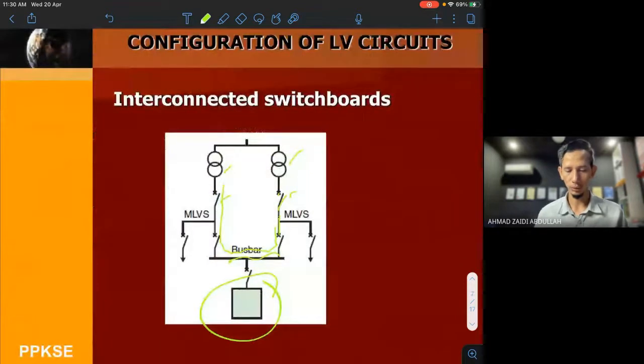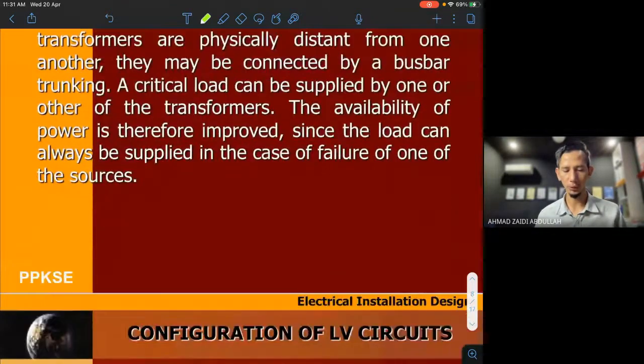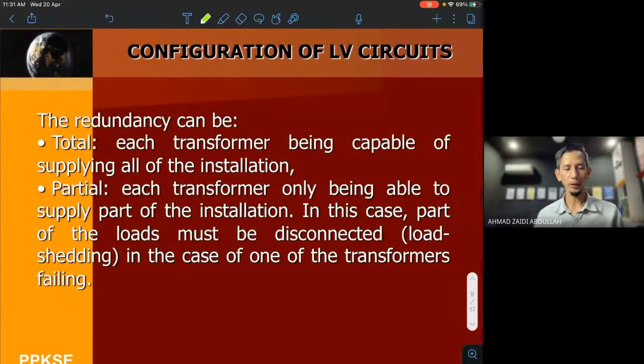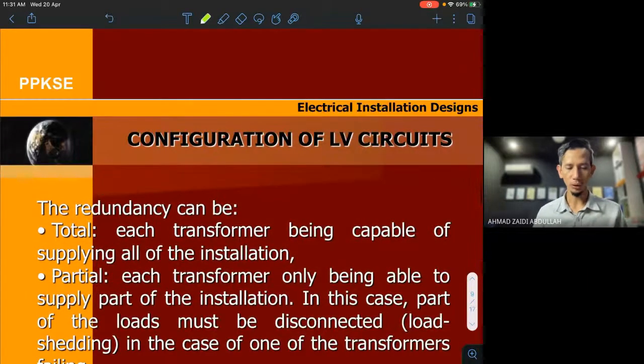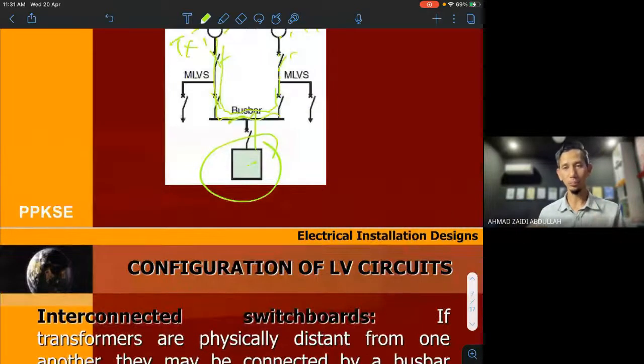So the availability of this load, it can get supply from this TX or this TX, transformer 2 or transformer 1. If you want to use transformer 1, you just close this circuit, so it can get the supply. Vice versa, if you want to use this supply. And then the redundancy can be, okay, total is the transformer being capable of supplying all of the installation. So redundant means it can have many times over.